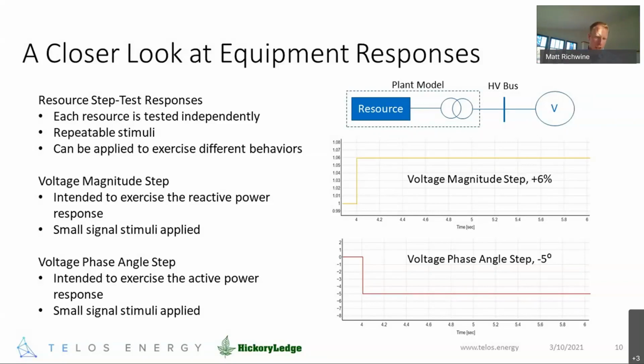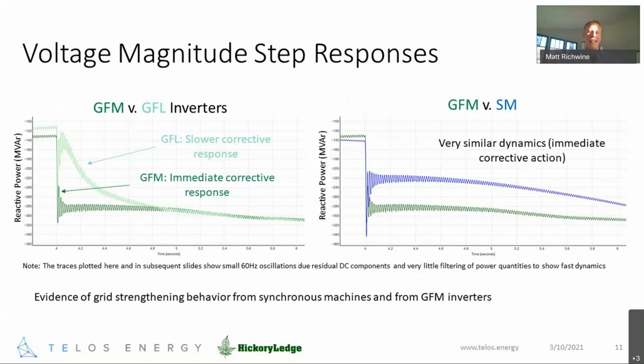So looking at first the voltage magnitude step responses. On the left, we're going to compare first the inverters, the GFM and the GFL, to the voltage step response. In all cases, you can see here that for a voltage magnitude step up, and granted where voltage phase angle did not change appreciably, the intent was it did not change, what you see is the reactive power response of all of the devices goes down. And so this is to be expected. This is a corrective action.